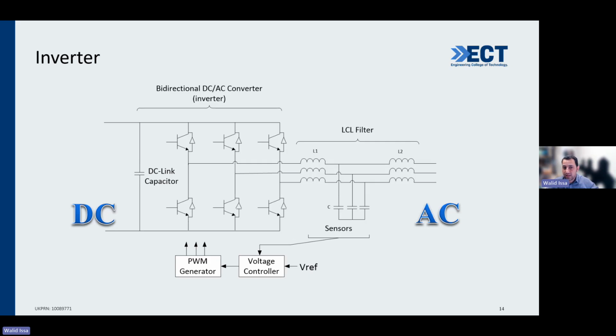What is the inverter from inside? It's a two-leg or three-leg switch arrangement, called power switches, made of IGBTs or MOSFETs. These convert by signaling, pulsed using PWM, or pulse width modulation, with a battery supplying the left side. Using the switches, they generate a modulated sine wave, which is filtered to remove high frequency components, leaving a pure 50 hertz sine wave that exactly matches the sine wave from your grid supply. This structure enables integration of other sources into the grid.